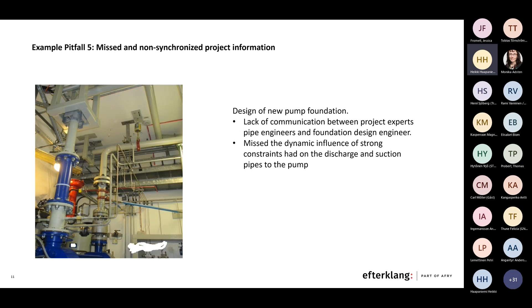And like Rainer mentioned here, the foundation is very important when it comes to design. We also had a rotor dynamic model in this project, modeling the pump. And it is very important to consider both the foundation and the pipe supports, because in this case the pipe support becomes stiffer than the foundation. So it's like an upside down foundation. So that influenced the pump vibrations a lot.